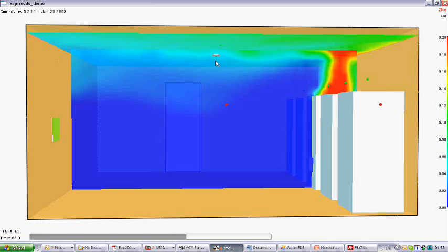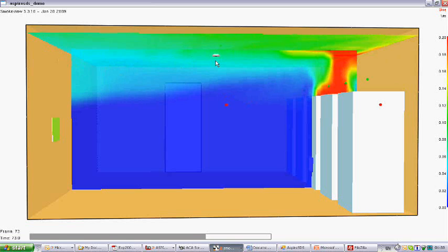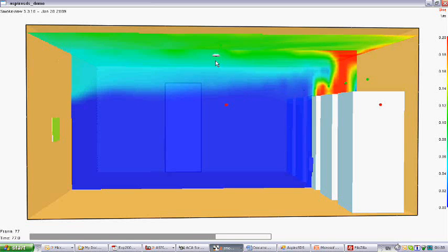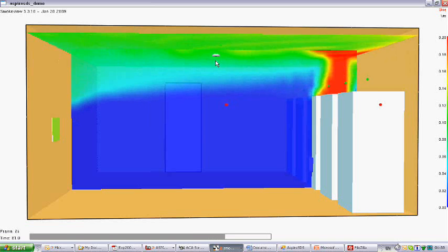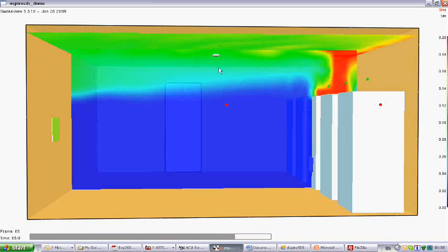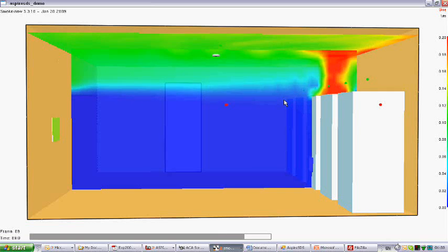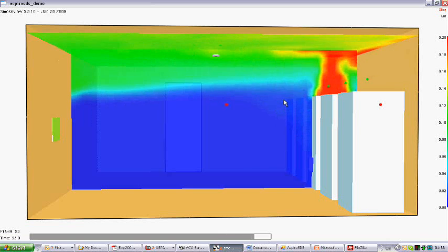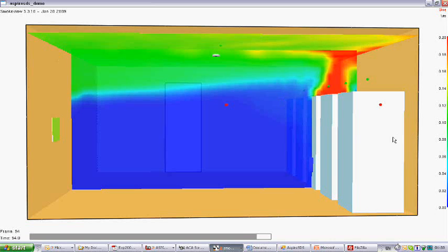Now this simulation is very simple, and the main objective is undoubtedly to demonstrate the power and usability of AspireSDS. However, while the fire is relatively simple and the geometry isn't complex, the fact is that the VESDA detectors with their sensitivity of 0.2% obscuration per metre will detect the fire much sooner than the point detectors with a sensitivity of 5% obscuration per metre.